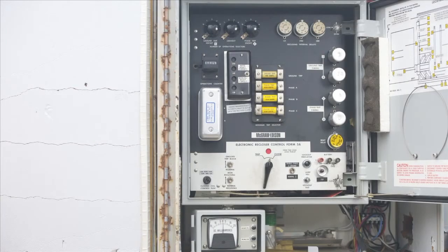Line current flowing through the recloser is sensed by 3 internally mounted bushing current transformers, one on each phase. When the phase current or the zero sequence ground current exceeds its programmed minimum trip value, the electronic control initiates the programmed sequence of recloser tripping and reclosing operations. If the fault is temporary, the control ceases to command recloser operations after successful reclose, and the control resets to the start of its operating sequence after a preset time delay.